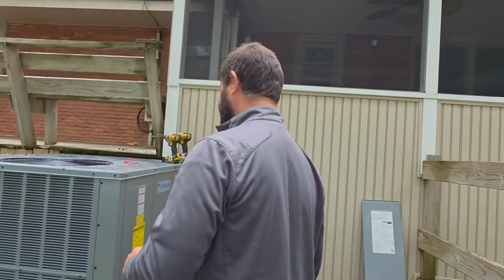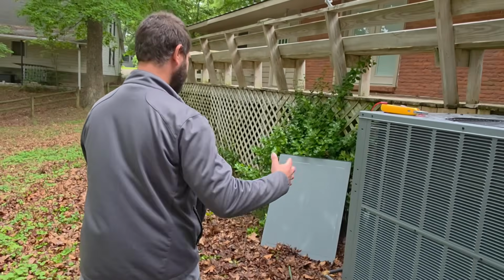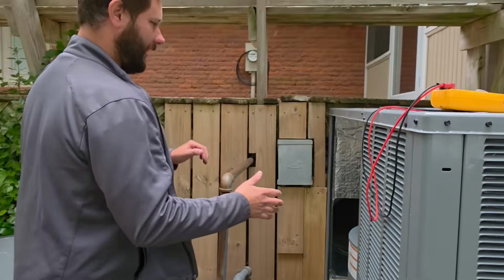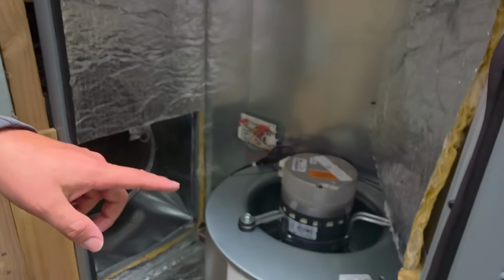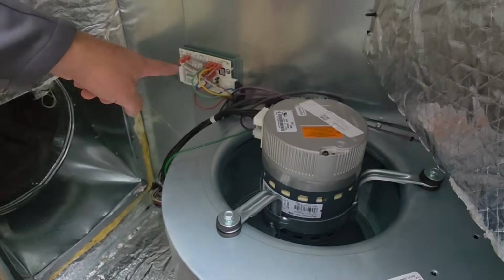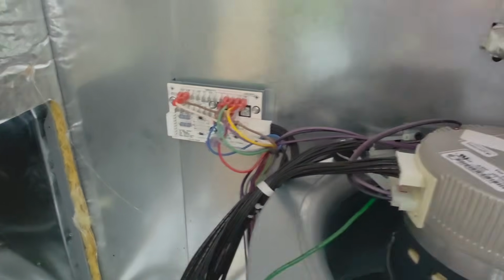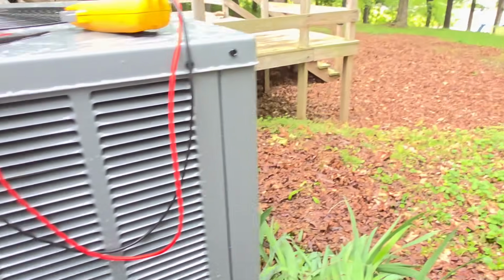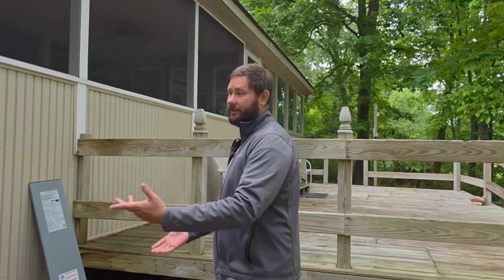Let's get started. So let me show you the blower first. The blower's running all the time. This is a variable speed motor, and we've got a variable speed control board right here. First thought is thermostat set to fan on, or the thermostat's calling, but something else would be running.